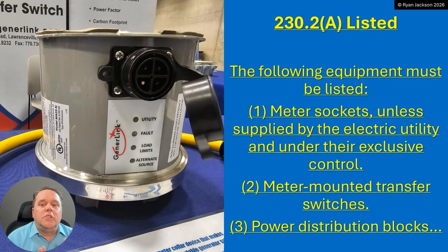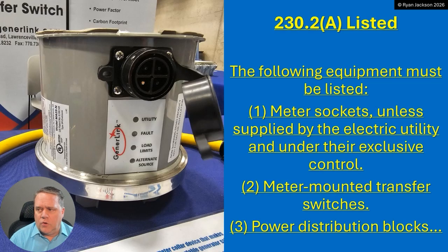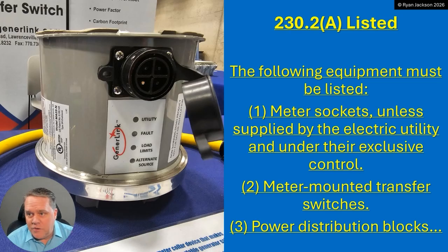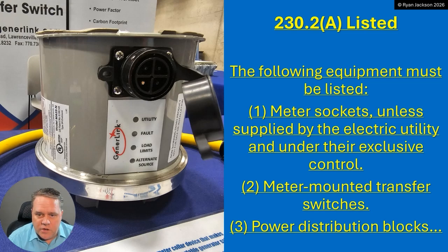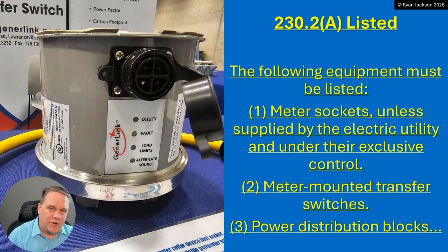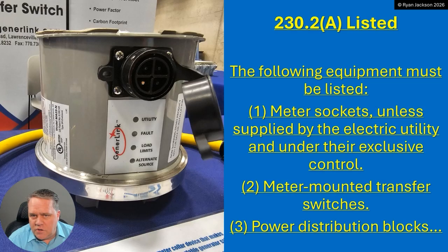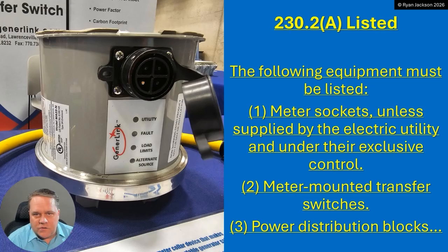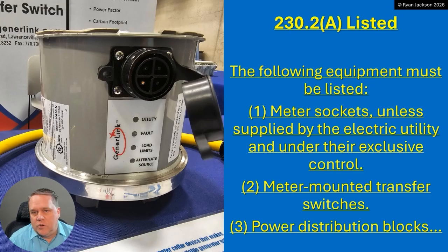230.2 has the listing requirements. All through Article 230, there was a bunch of different things that had listing requirements, and we moved them into the .2 section, which is what we're supposed to do. The stuff that got moved, I'm not going to spend any time on — it was already required, it's still required. The stuff that I think is of interest is what we're going to talk about. Item one: meter sockets have to be listed unless they're supplied by the electric utility and under their exclusive control.